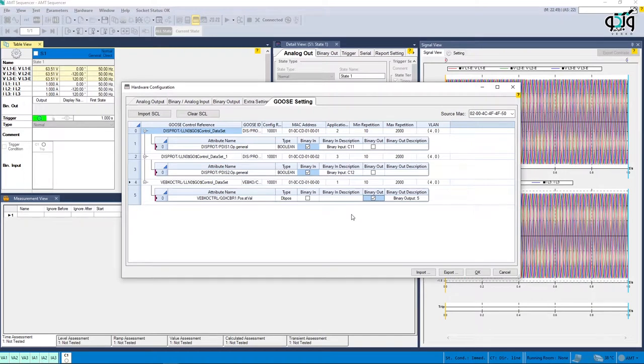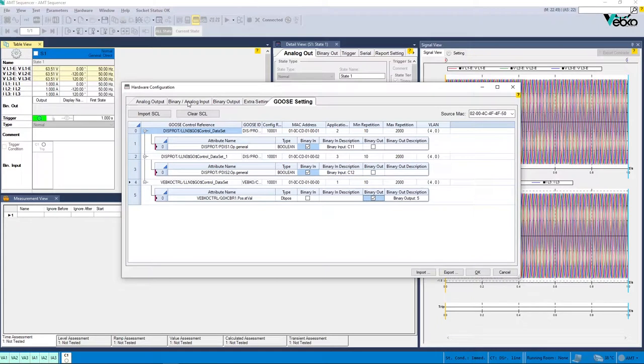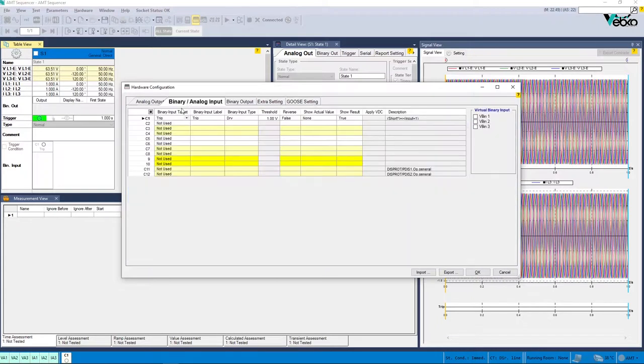In order to change the position of the breaker using the tester, binary output 5 is selected. The C1 binary is also wired to be used as a reference for comparing the time between trip zones 1 and 2.